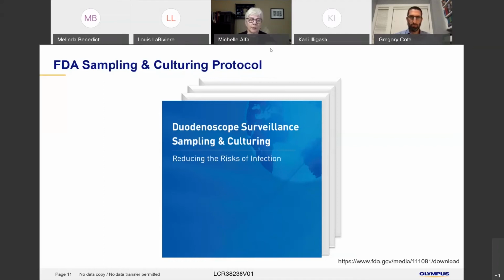And the final one is the lab component of it. How do you make it most sensitive? The idea of concentrating it, like the whole sample should be cultured, not just a drop of it, which is historically what a lot of the published data was based on, because that's not a very sensitive method. So I would say that prior to 2018, when the FDA, CDC, and ASM protocol came out, there was a huge variability in the efficacy of the sample extraction from the endoscope and huge variability in the sensitivity of the culture method.